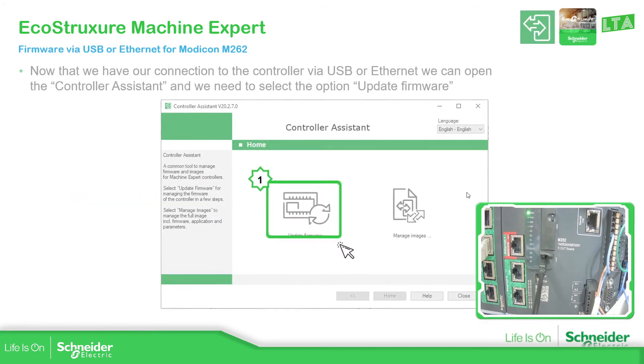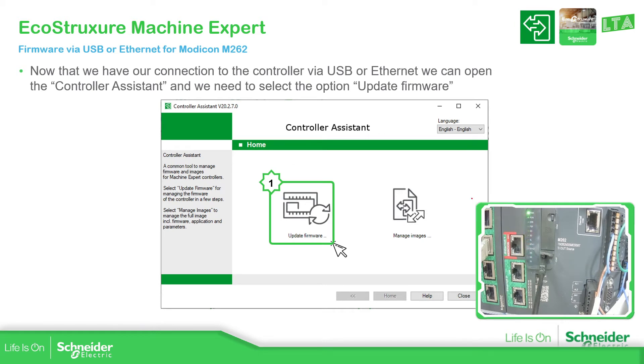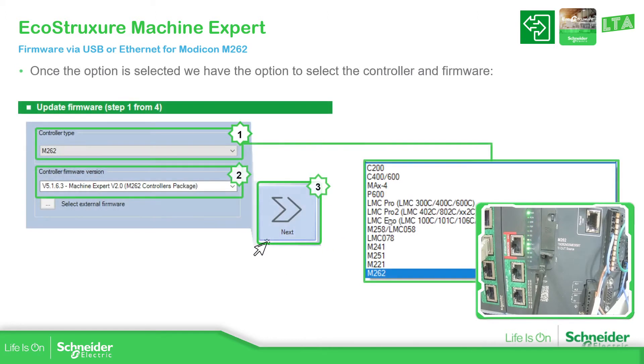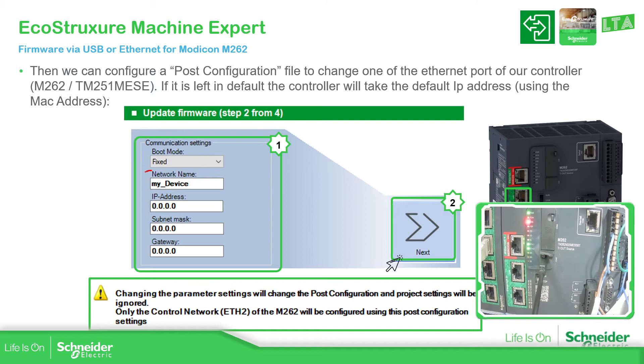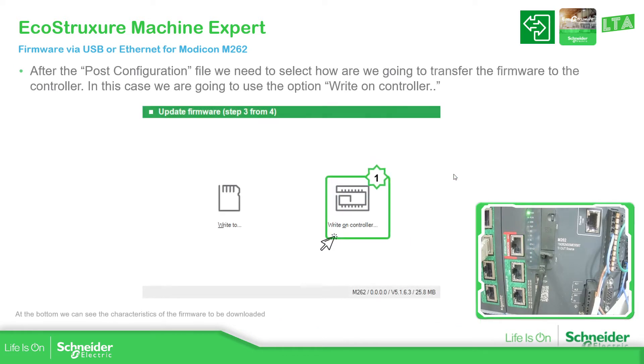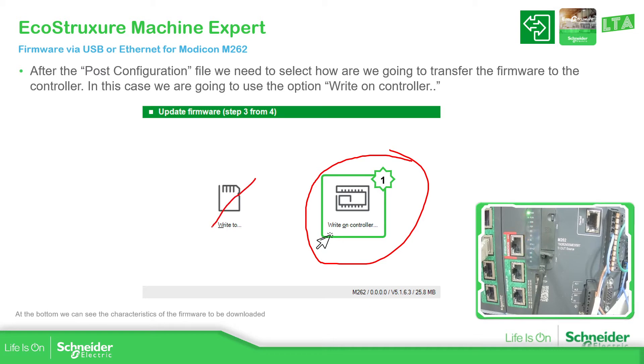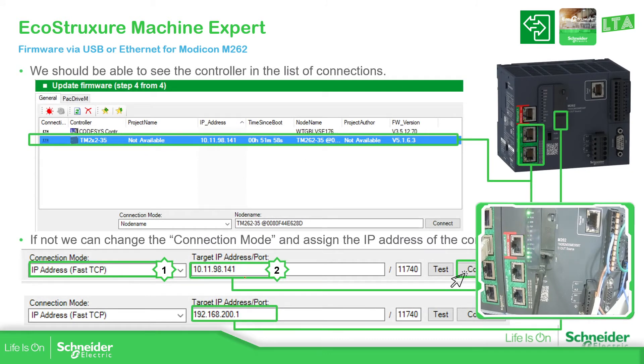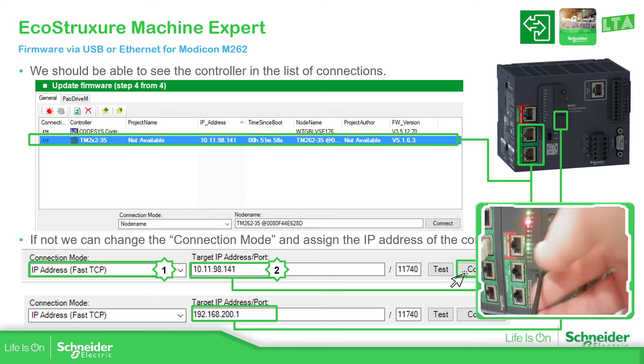Now that we know we have the possibility to connect, it's time to open the Controller Assistant to log in and change the firmware — select Update Firmware. We just need to select the controller we want to use, then we have the possibility to change the post configuration file for Ethernet port two. Select Next, then choose Write On Controller — not the SD card, because we're not going to use the SD card. Then check the communication as shown in the Machine Expert side.